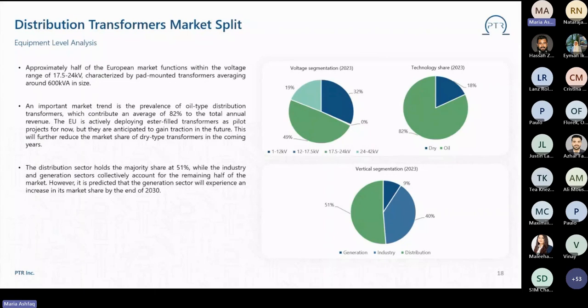Majority of the distribution system operators in the region have three-phase pad-mounted transformers installed in their network infrastructure, with an average size of 600 kVA compared to other regions. The US market is marked by single-phase pole-mounted transformers with an average size of less than 50 kVA. So the US and European markets are the two extremes: Europe marked by three-phase pad-mounted transformers, the US by single-phase pole-mounted transformers.